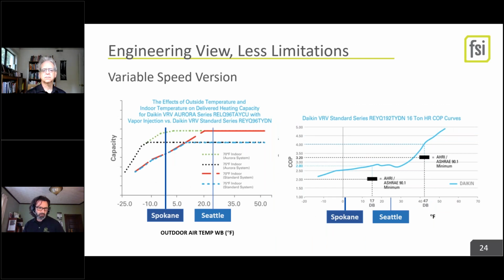This is Daikin's version of VRF, VRV. VRF is technically a Mitsubishi term. They trademarked it. But you can see for their regular system, Seattle is fine. You have full heating capacity down to Seattle design temps. You never need electric resistance. And if you do their fancier system, their better system, you can get down to near full capacity even in Spokane with their couple degree, nearly zero design temp. So this whole "heat pumps can't make it in cold heating" doesn't actually hold water, particularly if you're doing the better compressors.